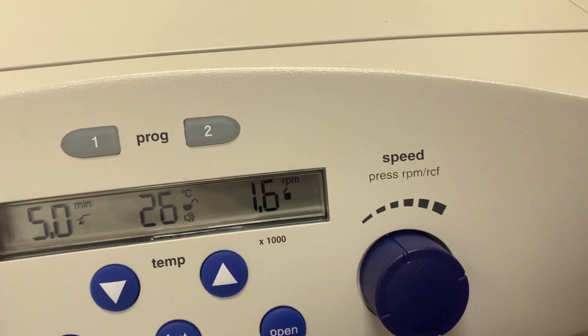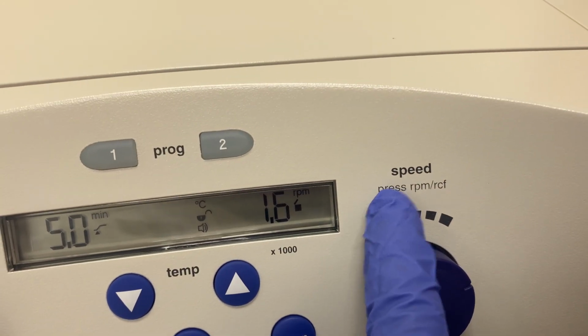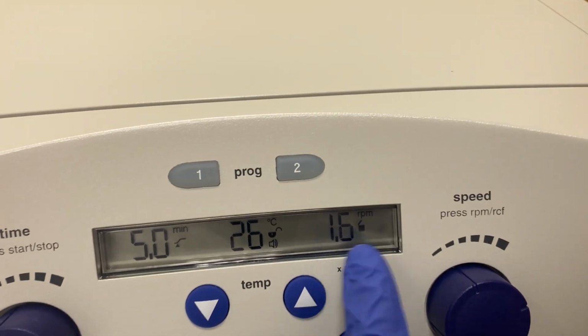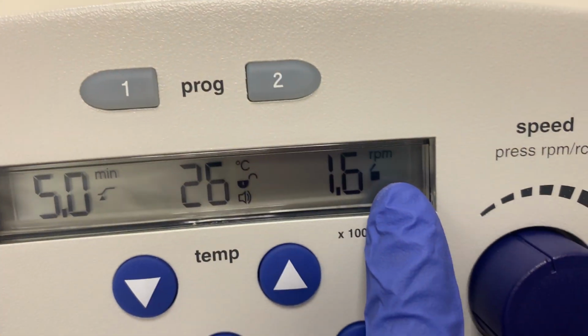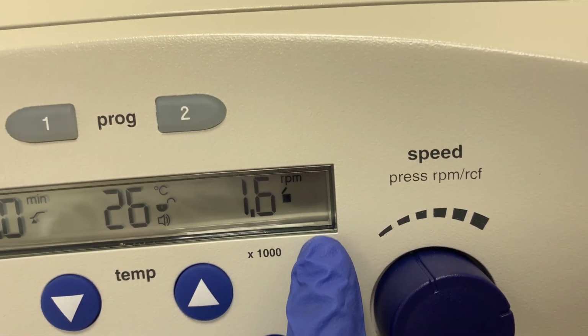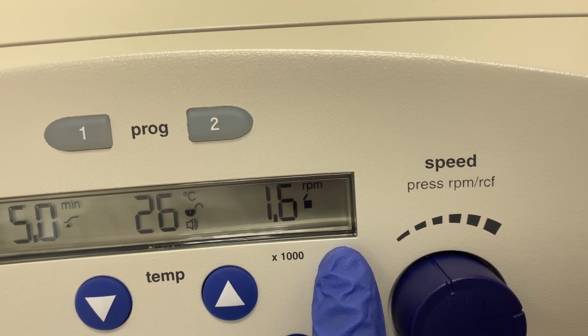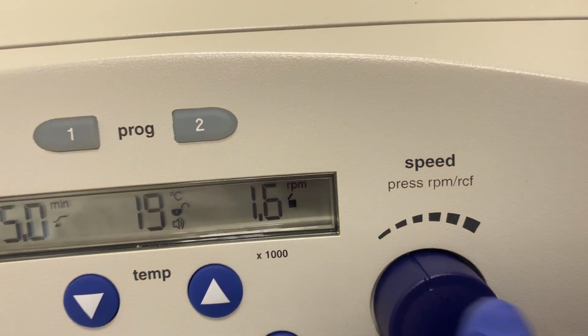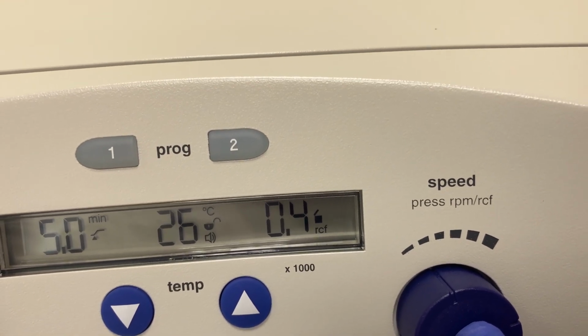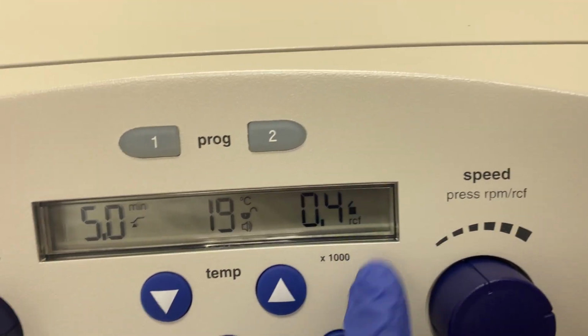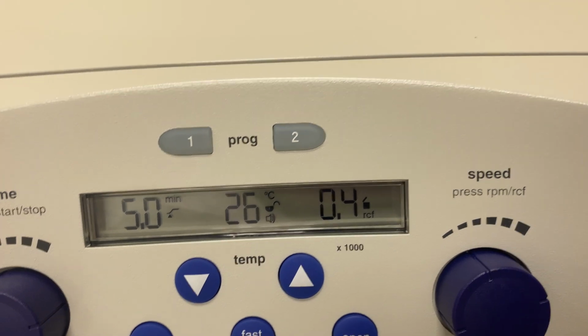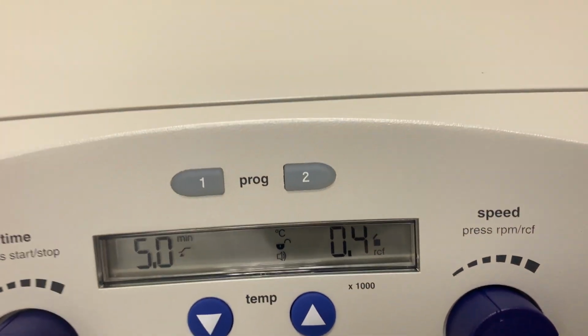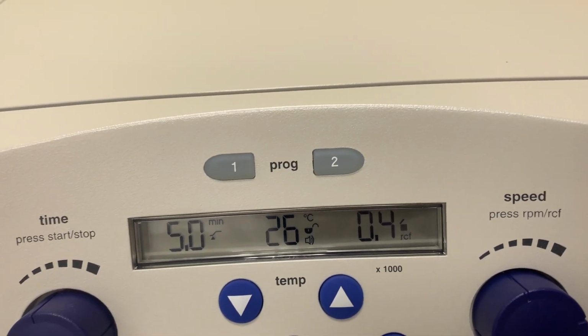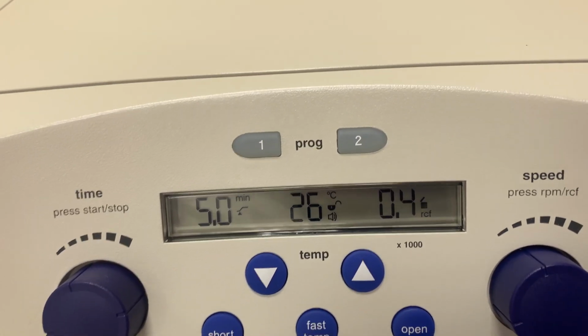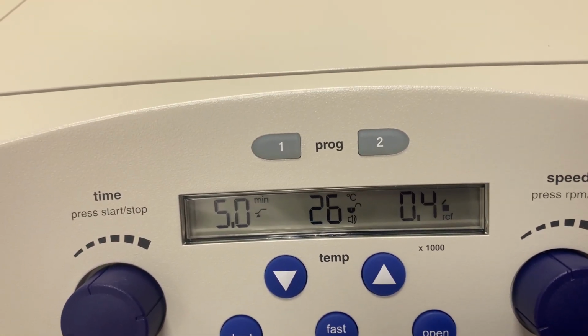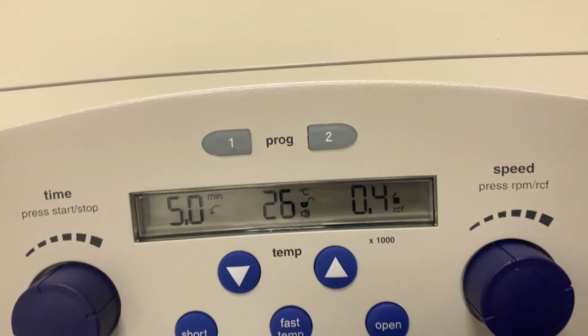How do we use RPM or change it? We have to press this button. There's a speed setting, press RPM or RCF. This is in RPM, so this setting is 1600 RPM. 1600 RPM equals 400 RCF, which is different from the bigger one. The bigger one is basically similar, 12,000 equals 11,000. So this one is like 3 times bigger in RPM.